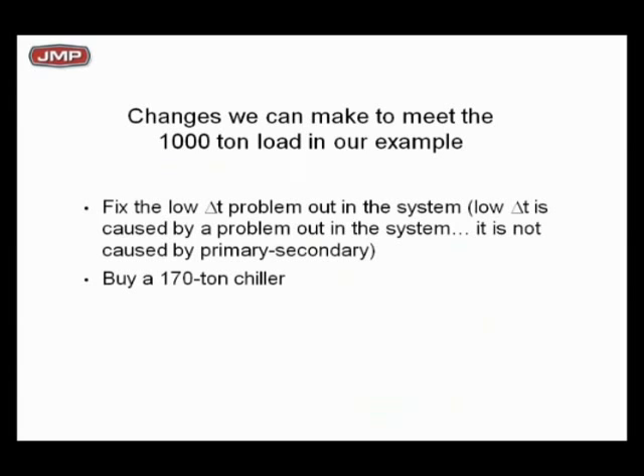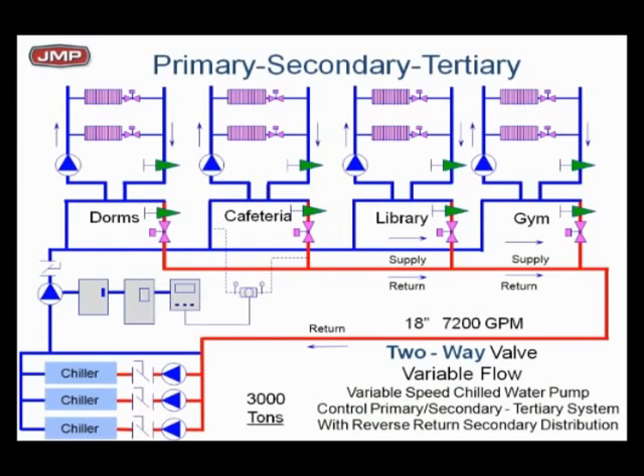I cannot repeat that enough. Get that idea in your mind. When you look at systems, think in terms of what the return chill water temperature should be. With variable flow and two-way valves, it should be at design or higher. So where are we going with all this? When you look at primary secondary systems, you need to understand the impact of varying the flow with two-way valves. You need to understand the impact of not having design return chill water temperatures.